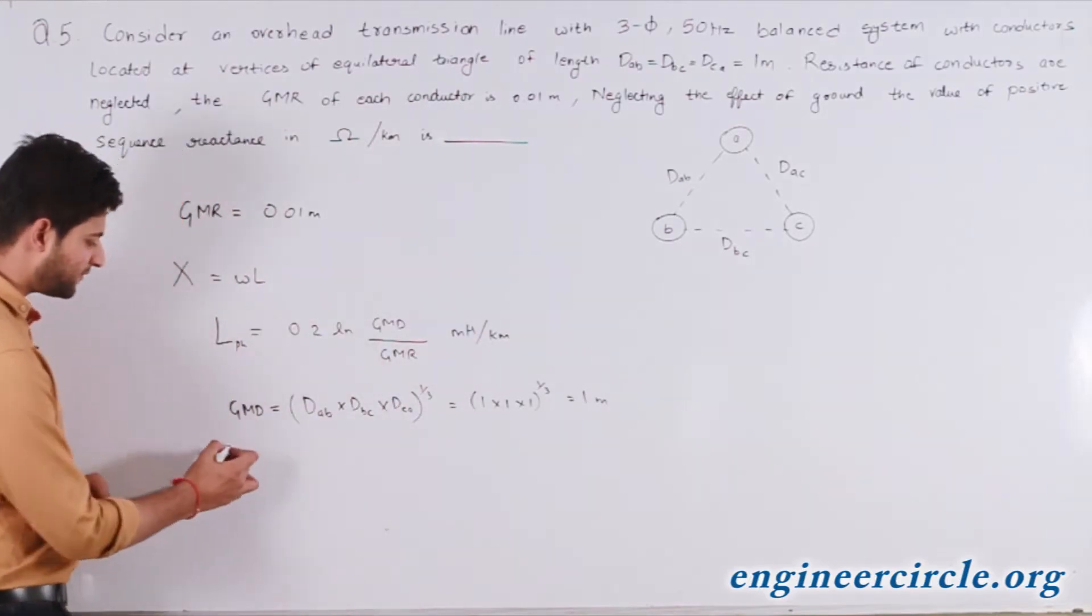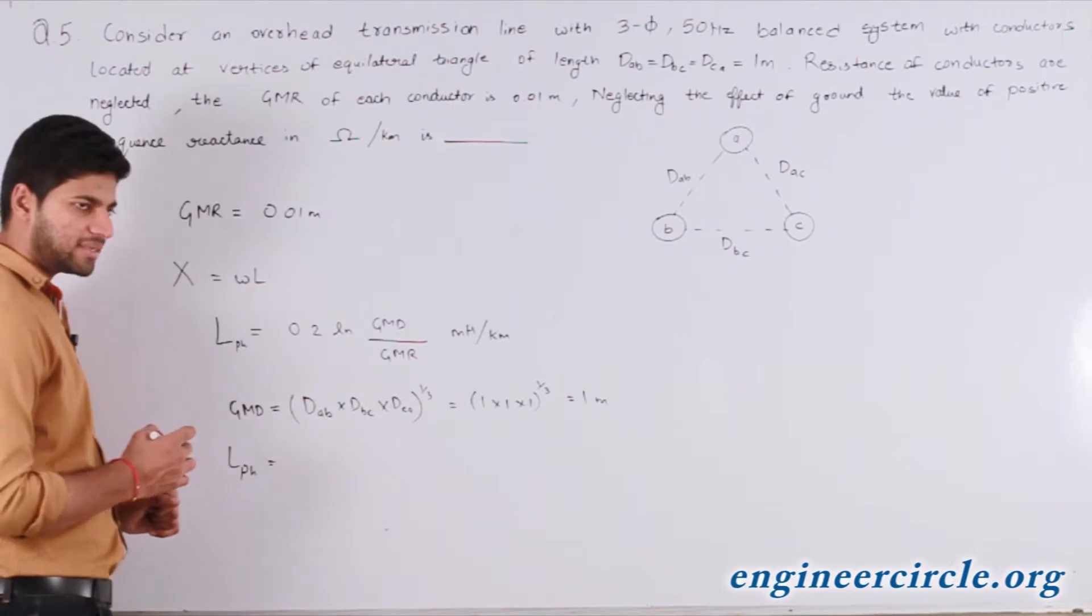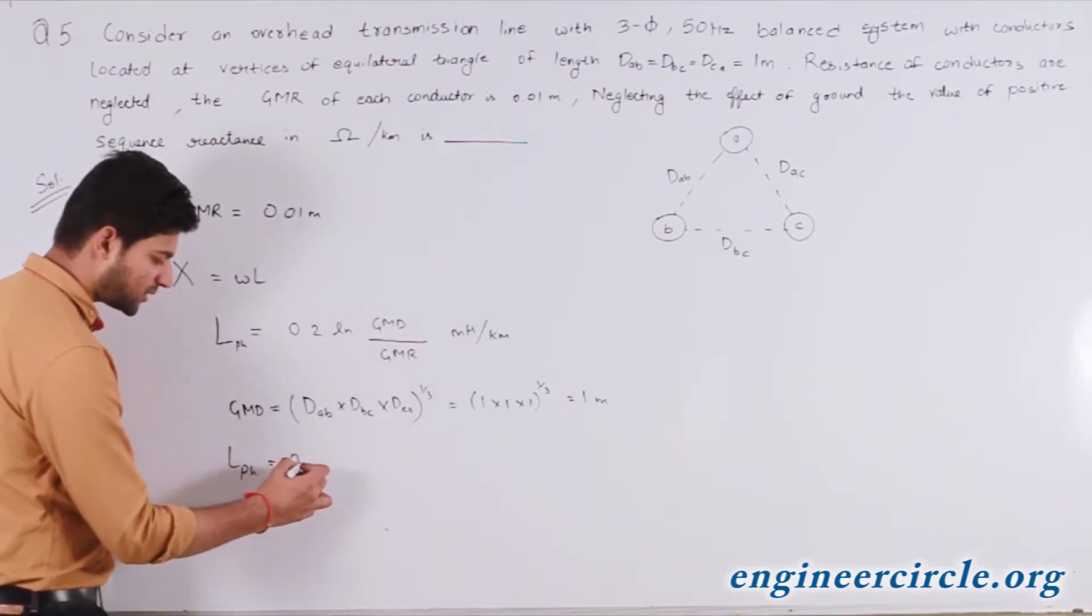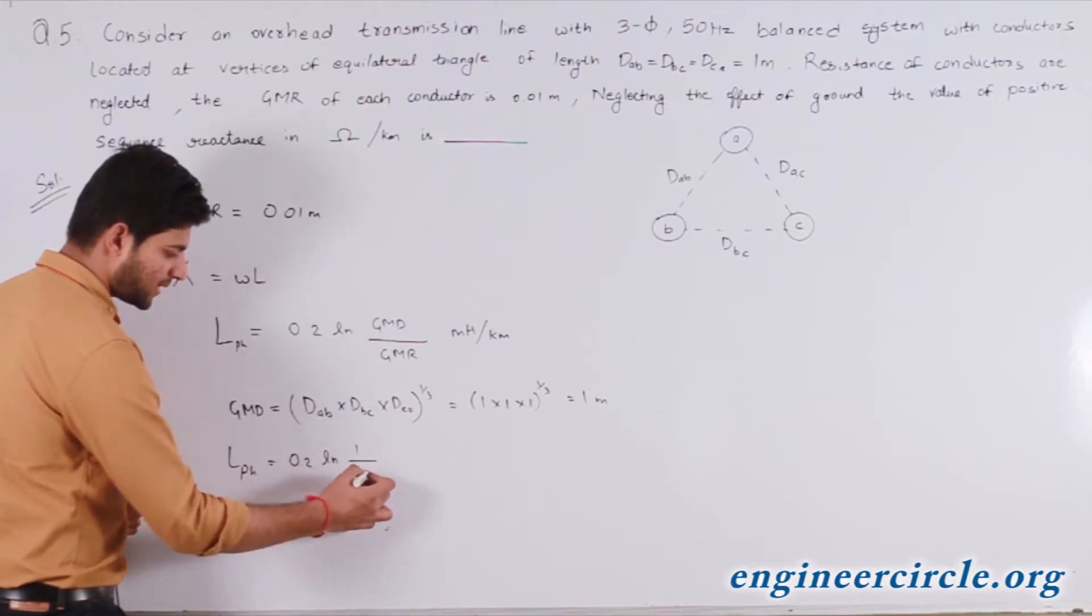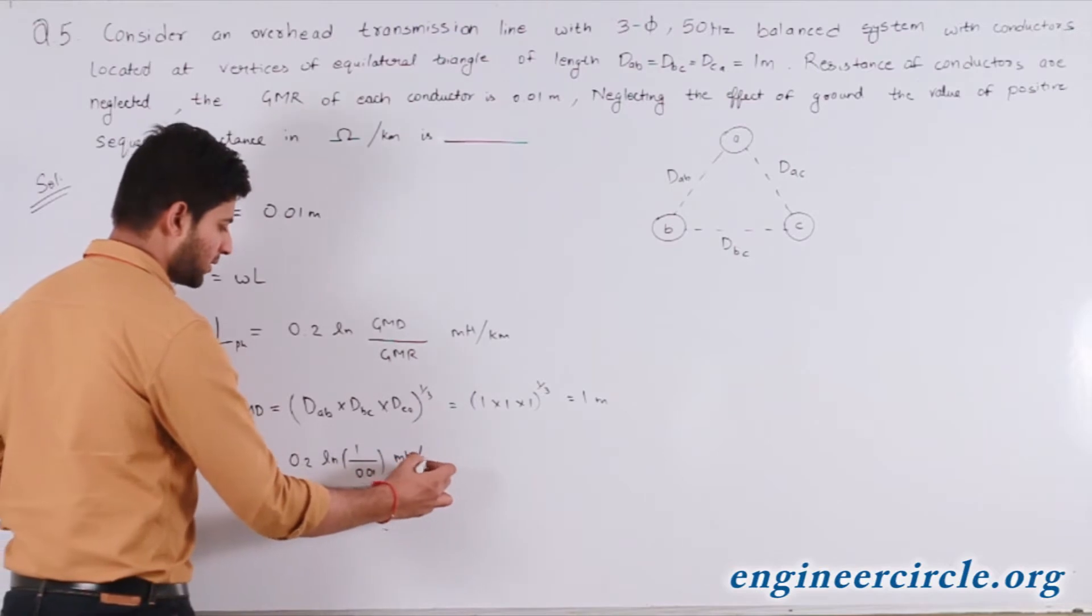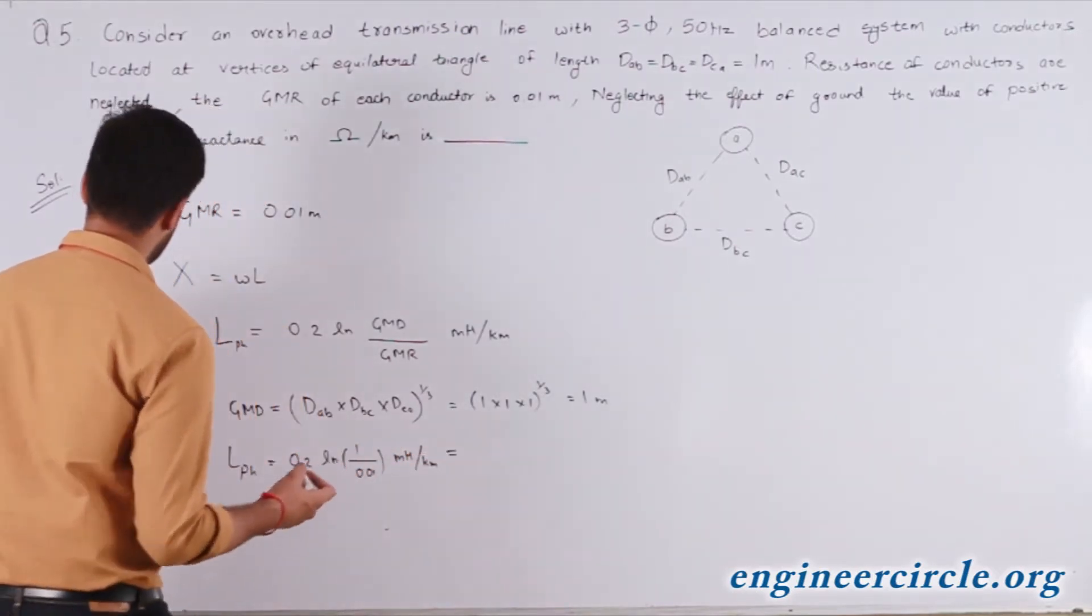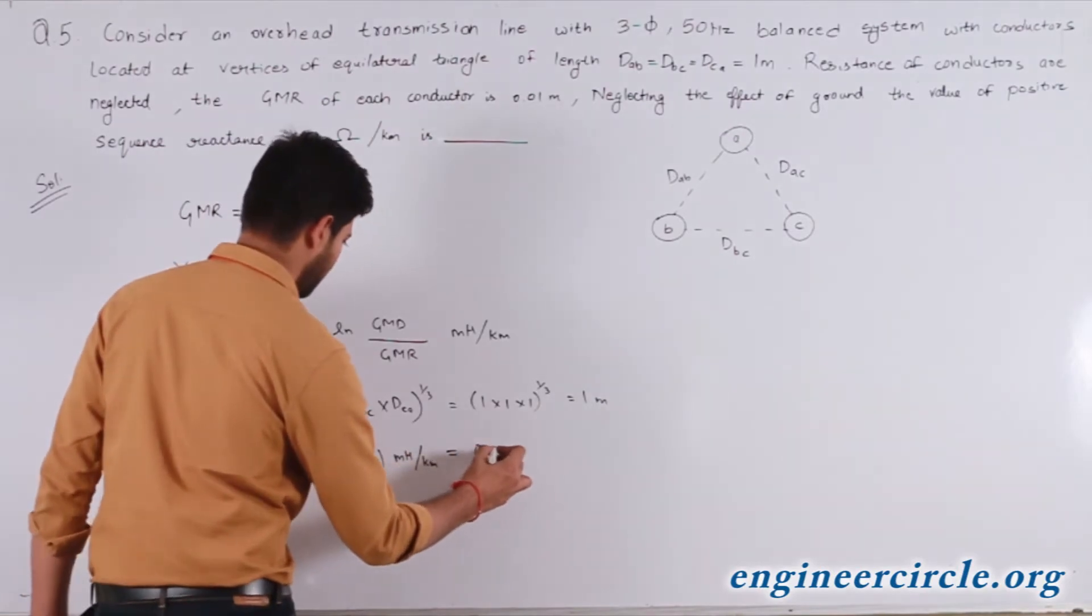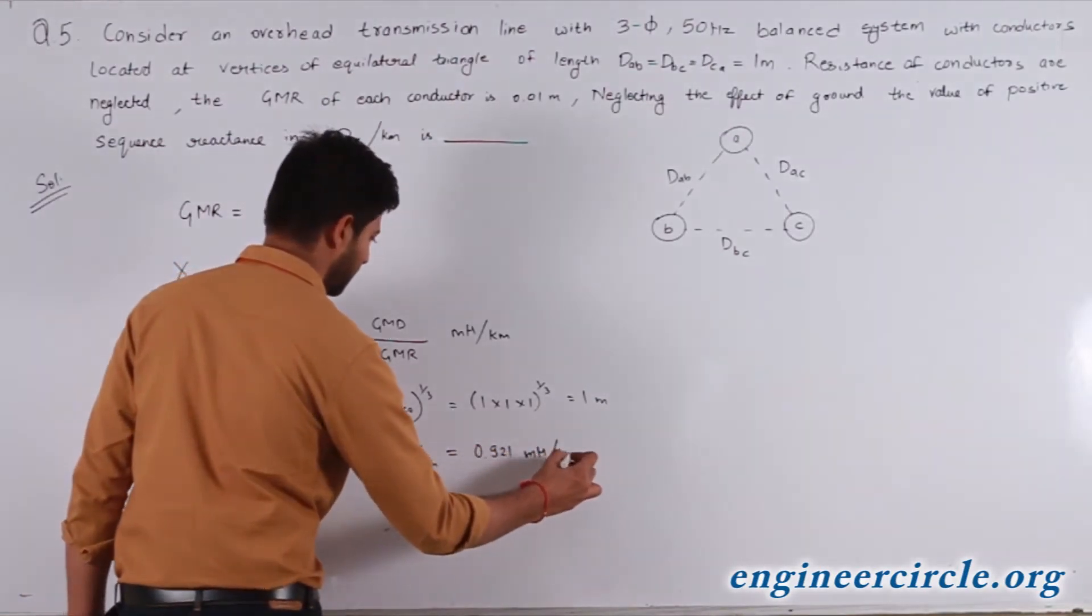So the per phase inductance here comes out to be 0.2 ln(GMD, this is 1, by GMR, 0.01) millihenry per kilometer. Solving this, we get the value of L to be 0.921 millihenry per kilometer.